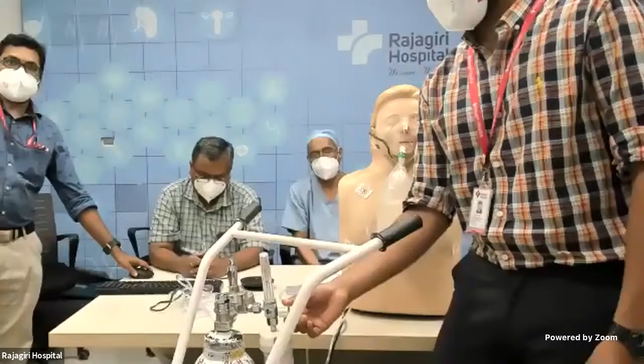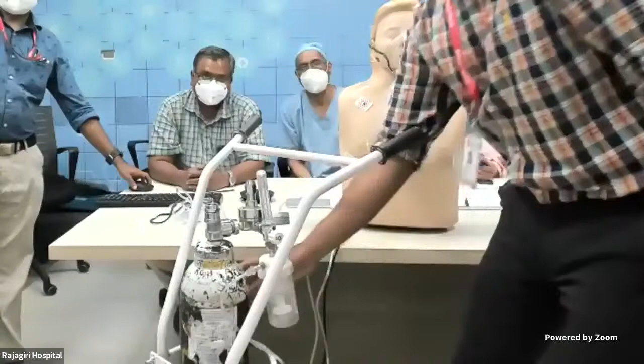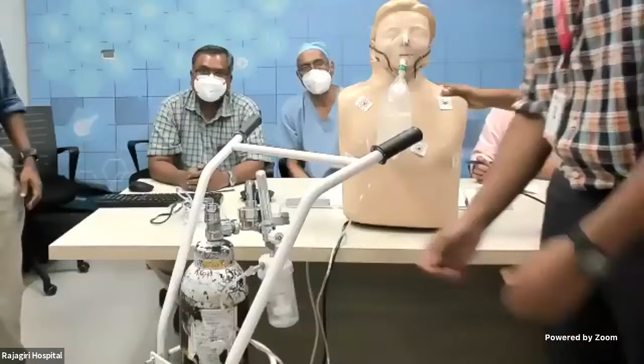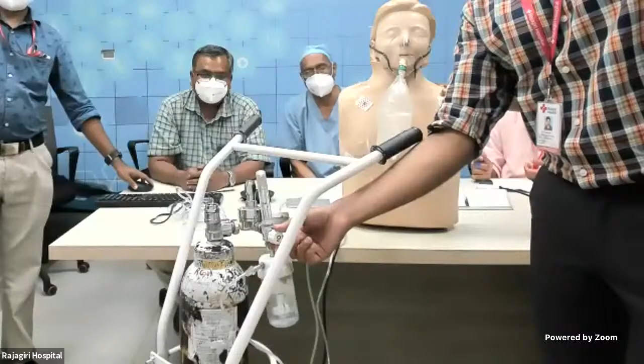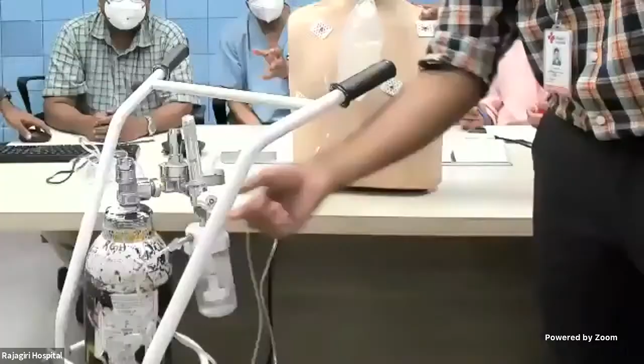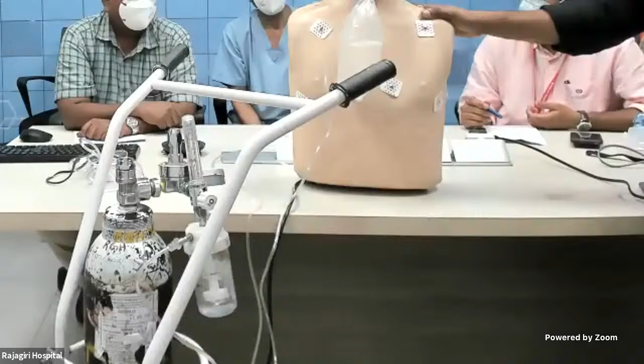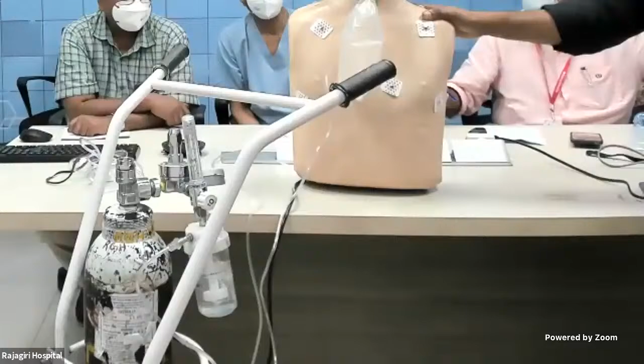No, I just wanted to show that this is coming through a bottle with the humidifier water there, and this is the commonest source of oxygen that we used to have everywhere. Now, of course, these days we have got more hospitals with piped oxygen, but the oxygen that is coming through that water is important, that it humidifies it, isn't it? But is there anything that we have to be careful about in that maintenance of that bottle and the water? How often do you have to change it? Do you have to change it at all, or we can wait till it dries up?